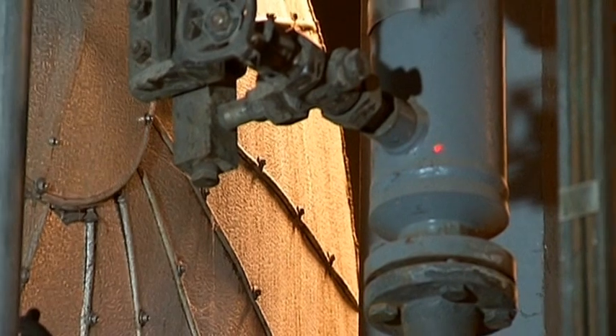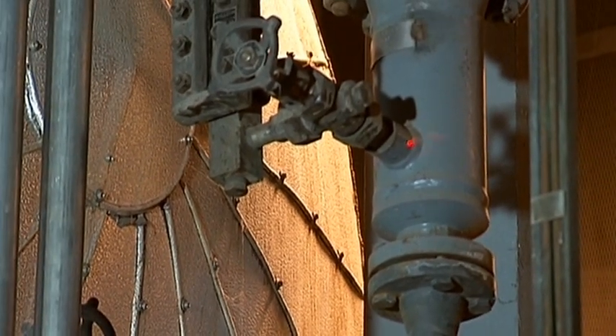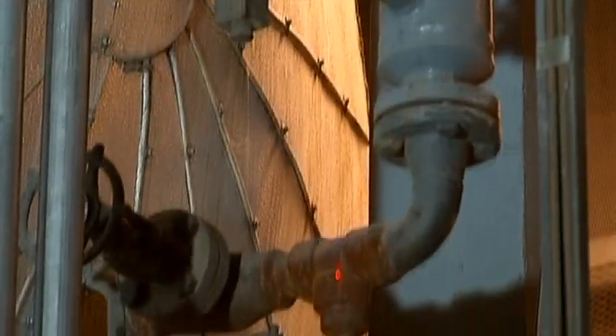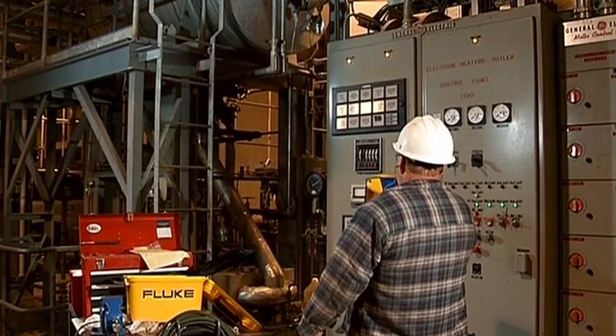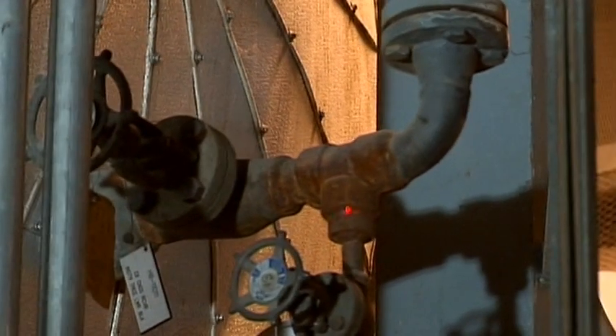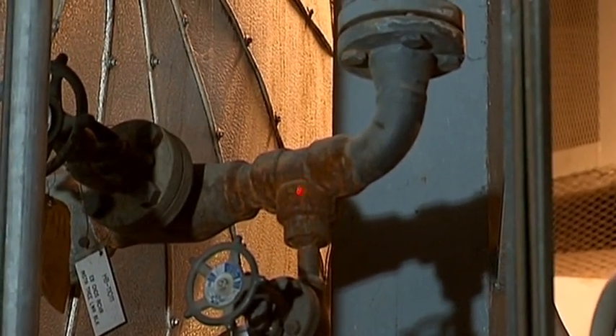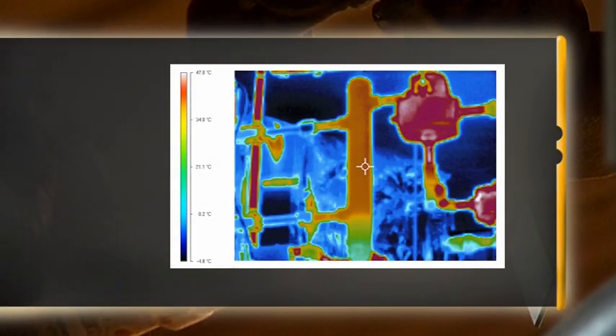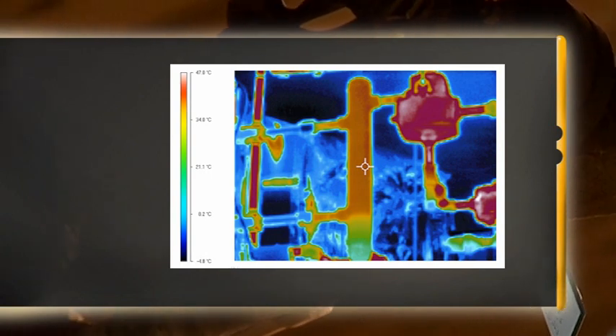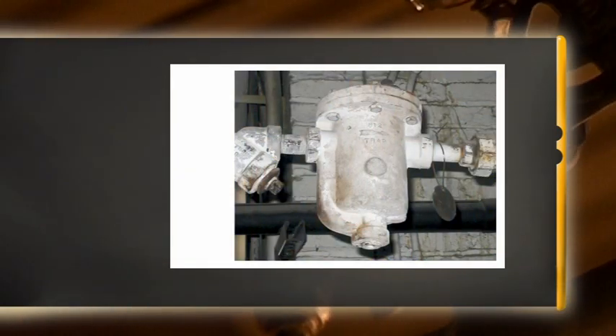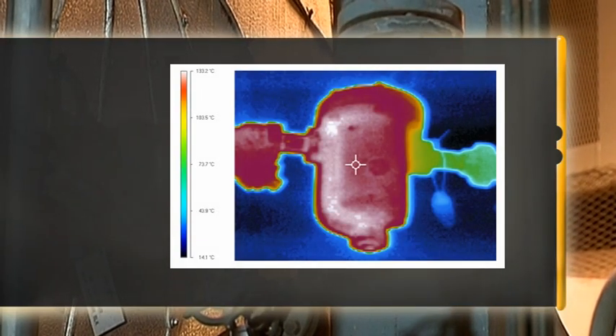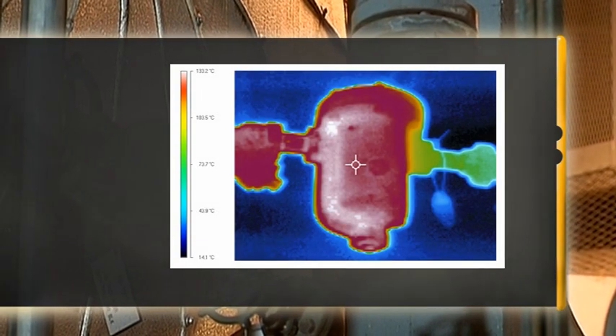If power is the most vital physical asset in your facility, then process is next in line. Pipes, vessels, and steam traps are not only hard to reach, but can be hazardous to be around. Using a thermal imager from a distance makes measuring the temperature of these components much simpler and safer. Thermal images reveal the comparative temperatures of system components and how efficiently and effectively they are operating. Thermal inspections help increase the detection rate of problems in steam systems, for example.